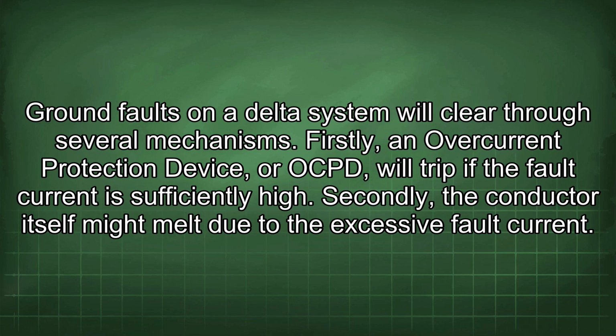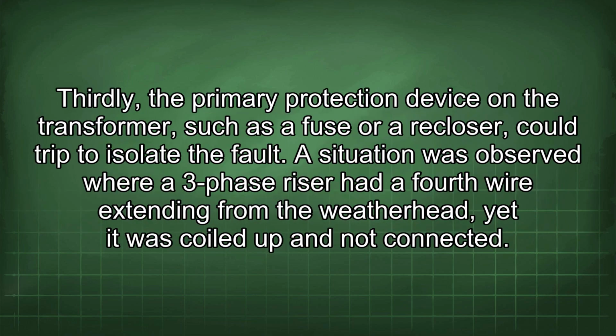Firstly, an overcurrent protection device, or OCPD, will trip if the fault current is sufficiently high. Secondly, the conductor itself might melt due to the excessive fault current.